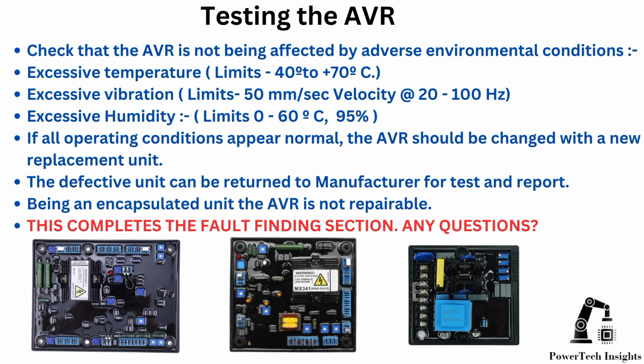If all operating conditions appear normal, the AVR should be changed with a new replacement unit. The defective unit can be returned to the manufacturer for test and report. Being an encapsulated unit, the AVR is not reparable. This completes fault finding of a 3-phase AC alternator.